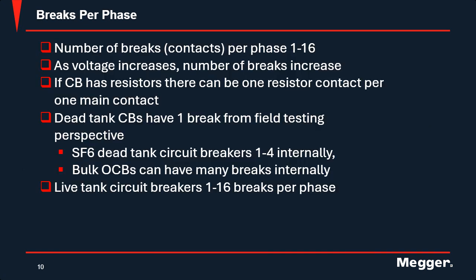So now we've talked about live tank, dead tank, and the operating mechanisms. Let's talk about breaks per phase. Breaks per phase, or interrupters, are used to divide the stress during opening or closing operations on the main contacts or the secondary contacts, also known as arcing contacts. We'll talk a little bit more about that when we get into dynamic resistance measurements. The number of breaks per phase can go from 1 to 16 depending on if it's a live tank or dead tank. As the voltage increases, generally the number of breaks increases, like I said, to help clear off that stress during opening or closing.